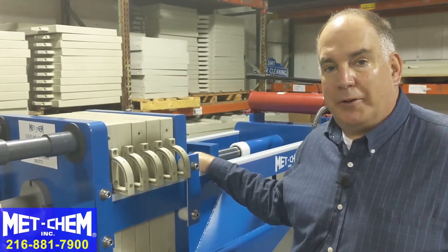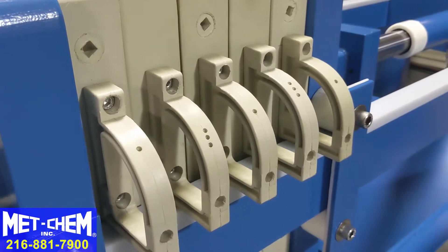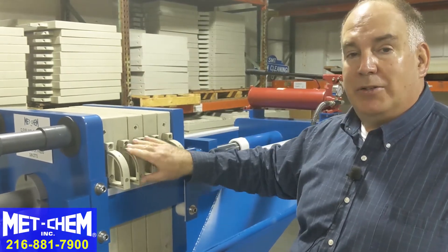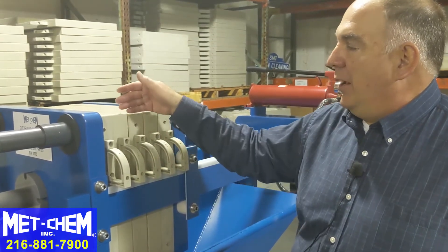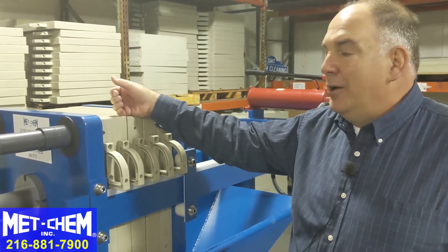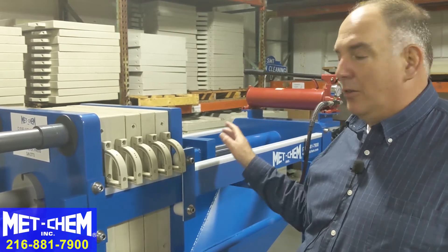There are two kinds of plates in the filter press designated by either a one button or three button marking on the handles. As you walk by the filter press you can easily see the one-three-one-three-one sequence. Buttons are only on this side; if there's a handle not showing buttons, that plate could be in backwards. The one-three-one-three sequence is important for the air blowdown process, which pushes air through the filter cake appropriately. Both plate types should be sequenced one-three-one-three throughout the length of the press.